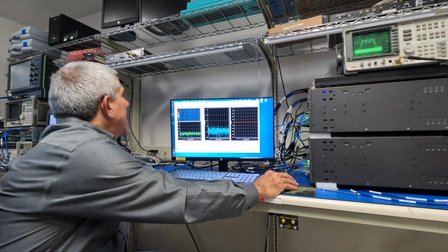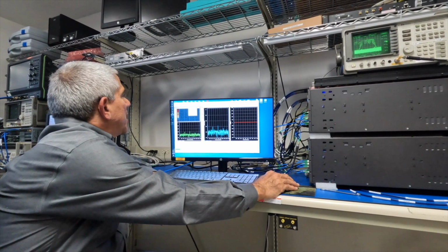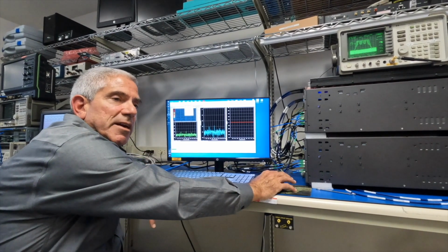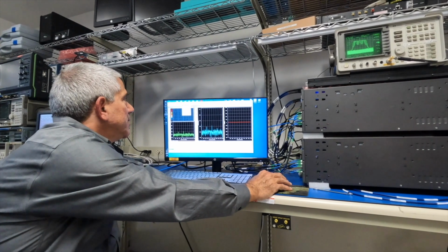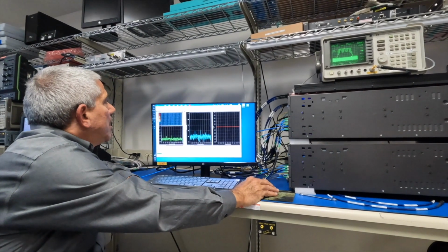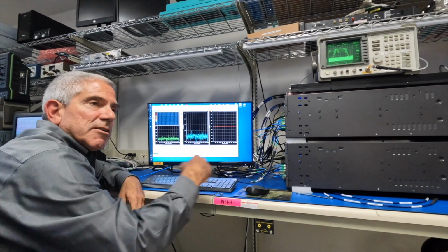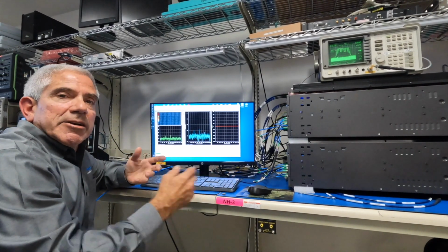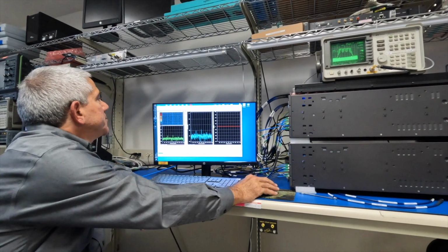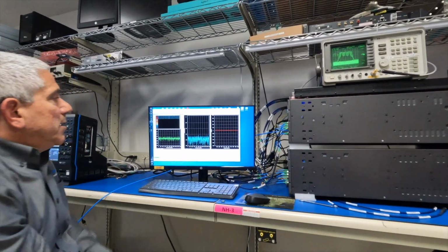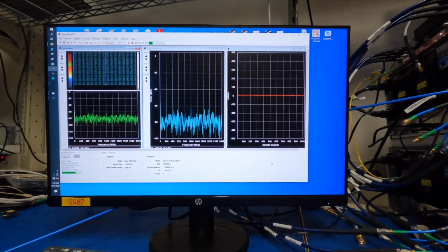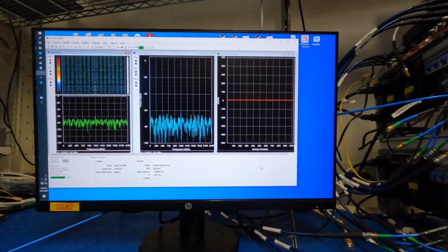So I'll stop the live capture, go to my playback mode, and load a snapshot record of the first 30 seconds of the 45 seconds we had captured. And you'll see when we play that back digitally, it will look like what we captured, which is the RF off at the beginning, and then we go right into the scenario of all the pulse CW, the frequency shift keying, the linear FM outputs. So here's the RF actually off at the beginning of the scenario until I turn the threat emulator on. And there's all of our RF.